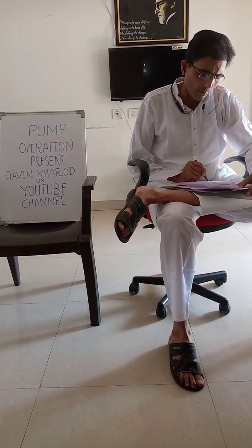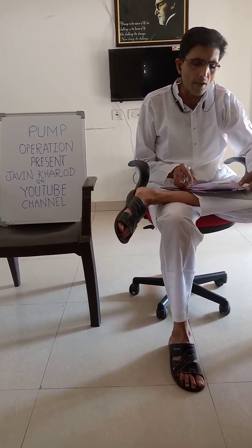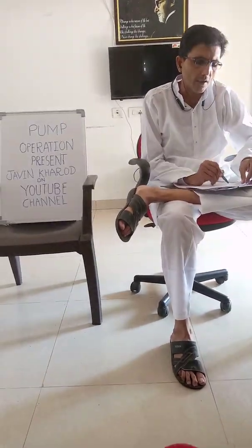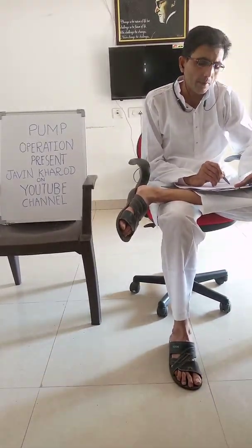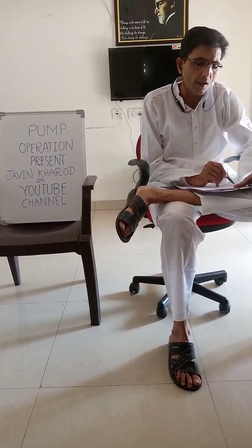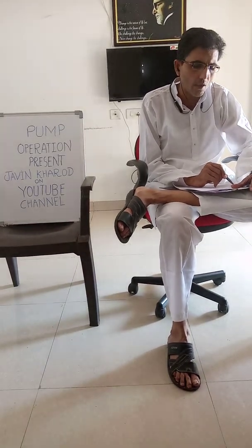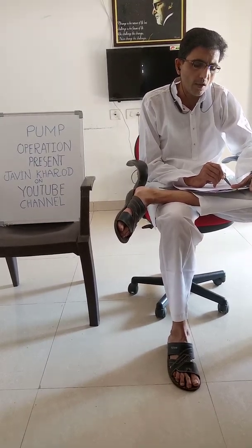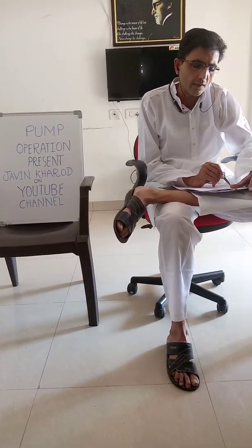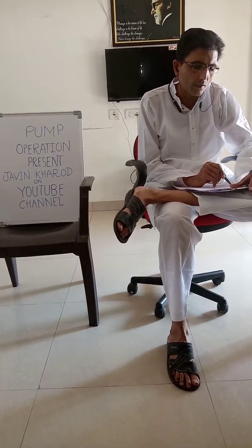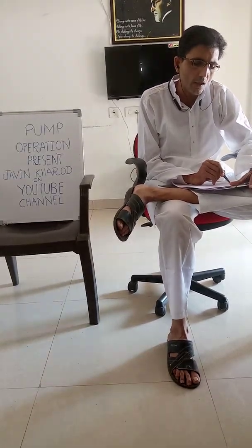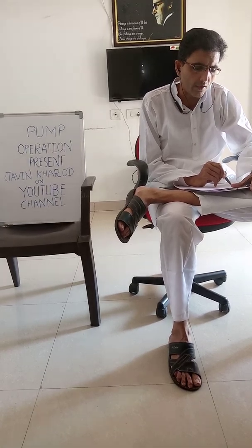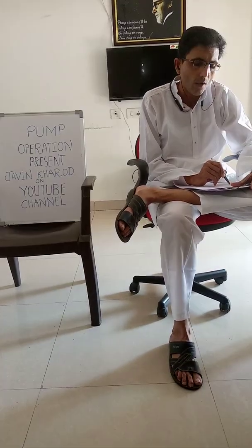The reciprocating pump. Typical reciprocating pumps are plunger pumps and diaphragm pumps. A plunger pump consists of a cylinder with a reciprocating plunger in it, with suction and discharge valves mounted in the head of the cylinder. In the suction stroke, the plunger retracts, the suction valve opens, and fluid is sucked into the cylinder. In the forward stroke, the plunger pushes the liquid out of the discharge valve.